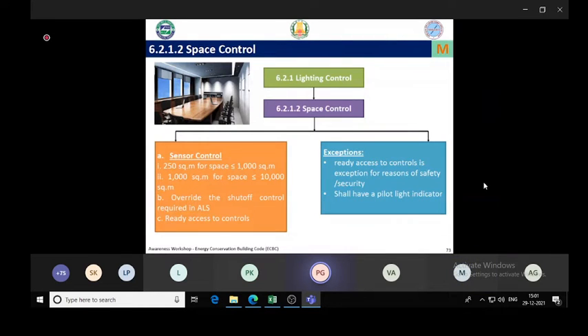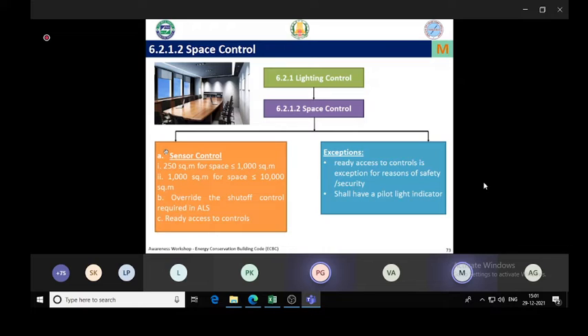Okay. The next requirement is to have a minimum number of light switches. So for example, if you have a space of 1000 square meter, then you need to have at least one switch for every 250 square meter. So for a 1000 square meter space, we need at least 4 lighting switches, controls. And if the area is more than 1000 square meter, then we need at least one switch for every 1000 square meter.